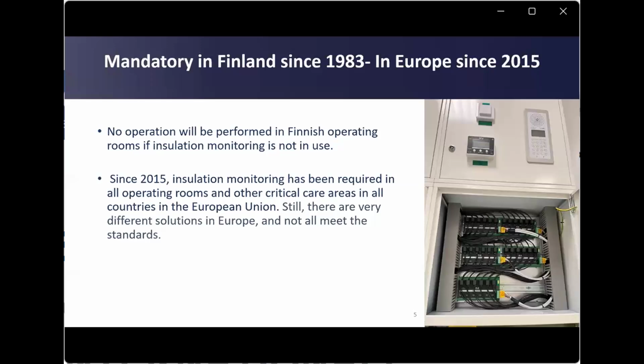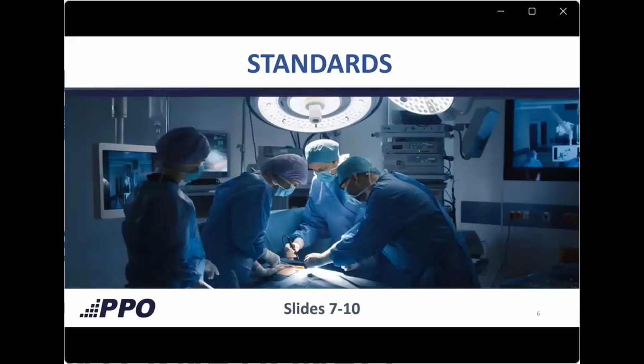No operation will be performed in Finnish operating rooms if insulation monitoring is not in use. Since 2015, insulation monitoring has been required in all operating rooms and other critical care areas in all countries in the European Union. Still, there are very different solutions in Europe, and not all meet the standards. Here is a short summary of the standards.